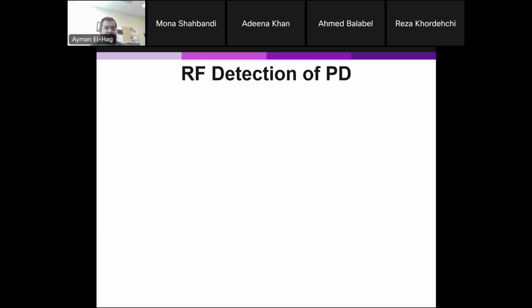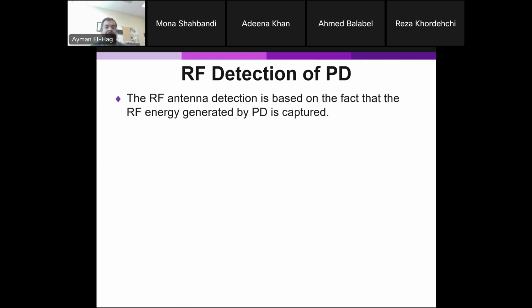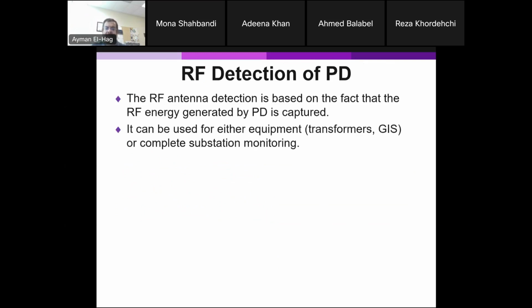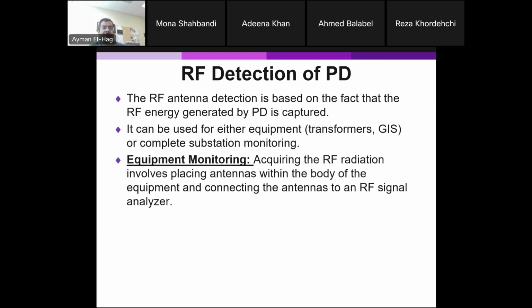RF stands for radio frequency, detection of the partial discharge. Okay. Now, as I said, here you will have radiated electromagnetic waves. So if you have an antenna, it can detect that type of radiation. Now, it can be used for internal devices, like PD inside a device like a transformer or GIS, or you can use it also for substation monitoring. Okay.